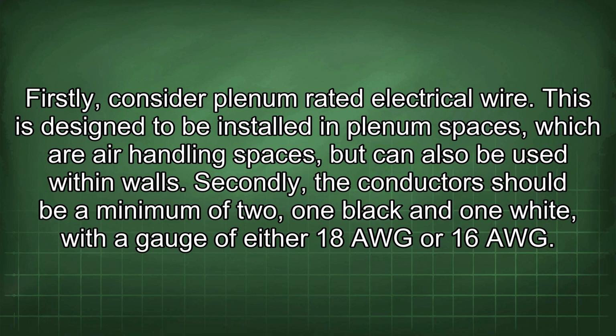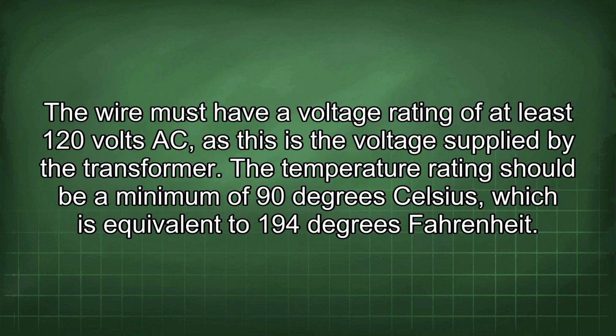Secondly, the conductors should be a minimum of two, one black and one white, with a gauge of either 18 AWG or 16 AWG. The wire must have a voltage rating of at least 120 volts AC, as this is the voltage supplied by the transformer. The temperature rating should be a minimum of 90 degrees Celsius, which is equivalent to 194 degrees Fahrenheit.